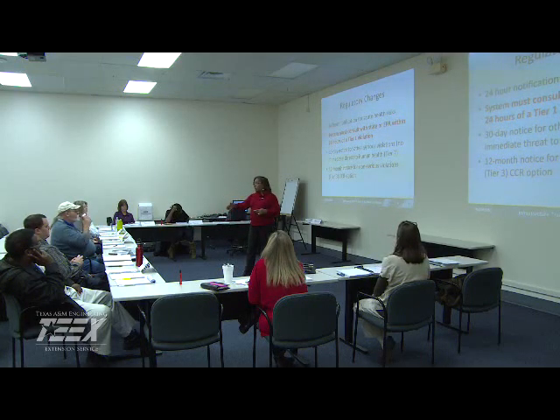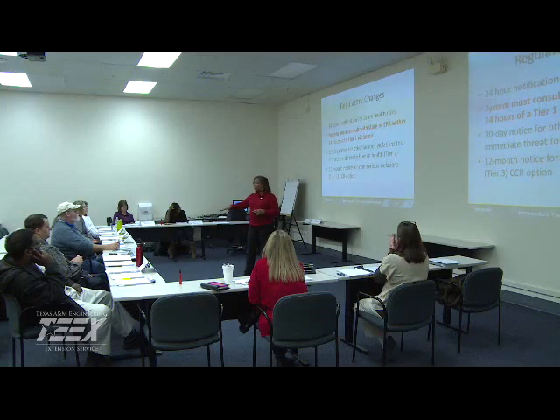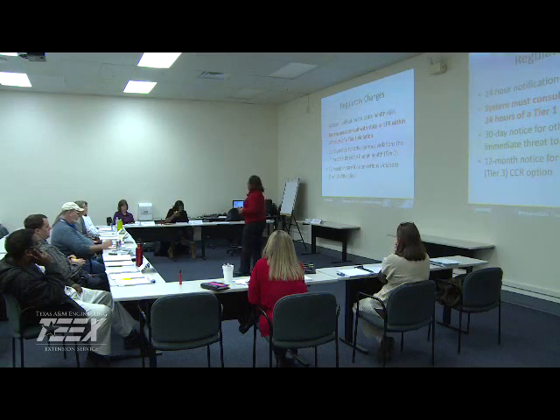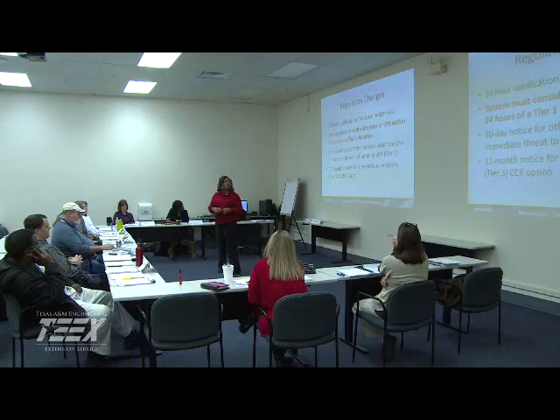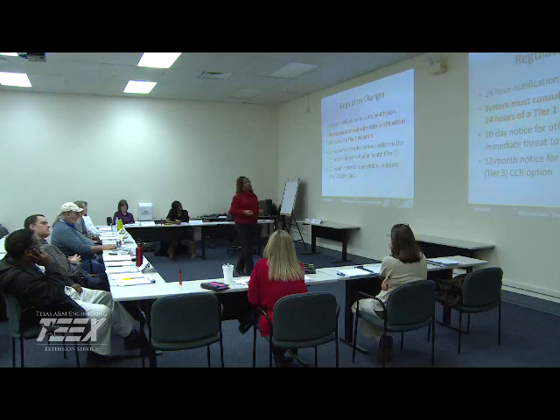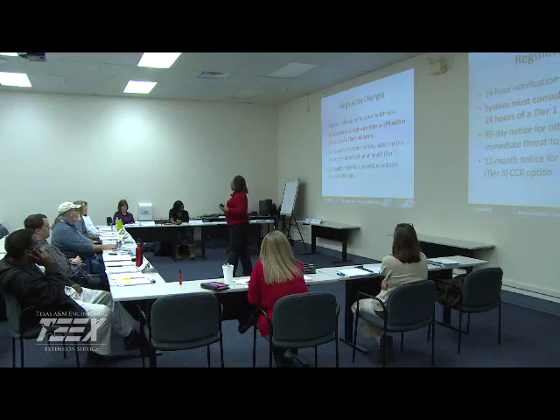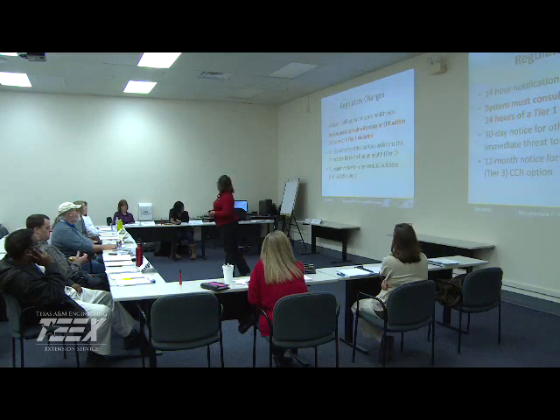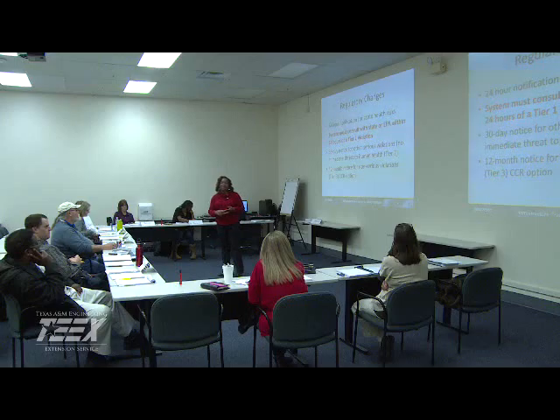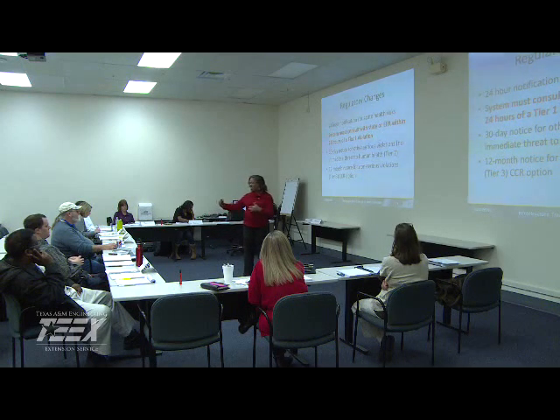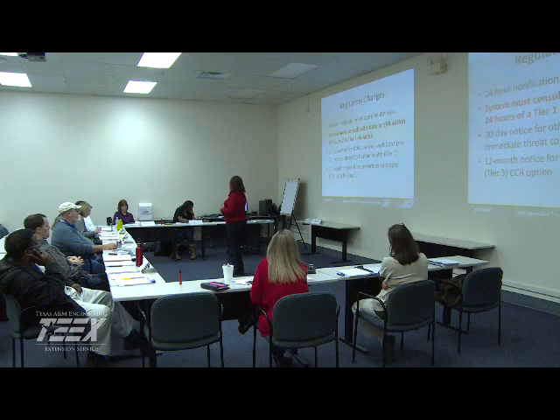Whenever E. coli or fecal coliform is present, you're looking at a Tier 1 notification. The system must consult with the state or EPA within 24 hours of a Tier 1 violation. E. coli and fecal coliform — that's a Tier 1. You're supposed to notify them as soon as you get word or by the next business day, which is within 24 hours, and then you notify the public within 24 hours on a confirmed test.